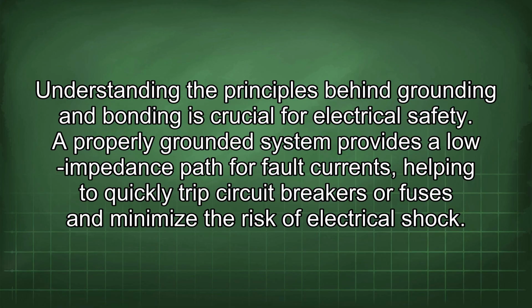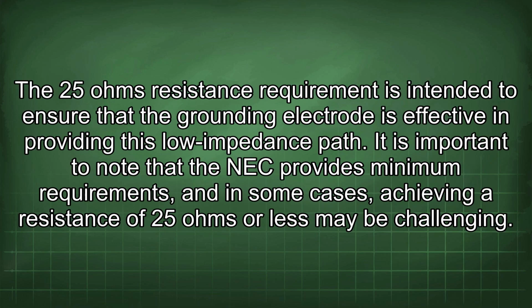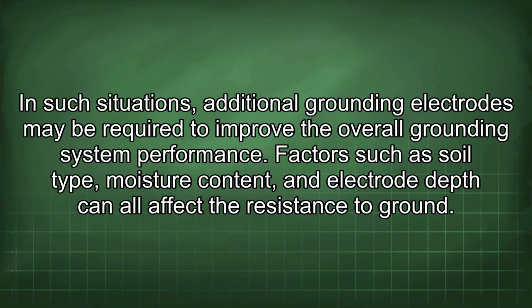Understanding the principles behind grounding and bonding is crucial for electrical safety. A properly grounded system provides a lower impedance path for fault currents, helping to quickly trip circuit breakers or fuses and minimize the risk of electrical shock. The 25 ohms resistance requirement is intended to ensure that the grounding electrode is effective in providing this low impedance path. It is important to note that the NEC provides minimum requirements, and in some cases, achieving a resistance of 25 ohms or less may be challenging. In such situations, additional grounding electrodes may be required to improve the overall grounding system performance.